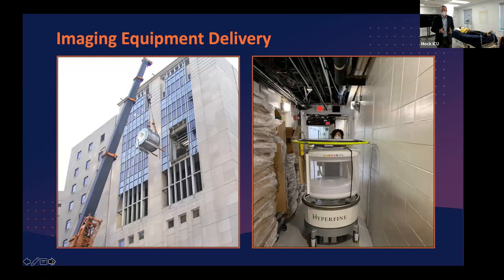Most of us know the day when a new MR system is swapped out in your hospital, because you see the trucks, the crane, the jackhammer, the cement truck — it's pretty invasive. With Hyperfine: five feet tall, three feet wide, weighs about 1,400 pounds — a very lightweight system. We wheel into the front door of hospitals. We fit on a standard patient elevator and through a standard doorway. If our mission was to go bedside, that commitment sets a whole bunch of design decisions — how wide our magnet would be, the gap between the two magnetic poles. We can be on site, back the truck up, unload, and be through training inside of a day. It's a new model for MR deployment.